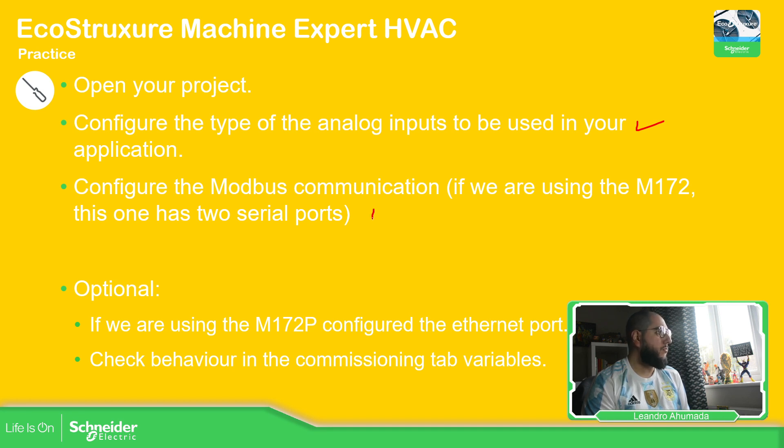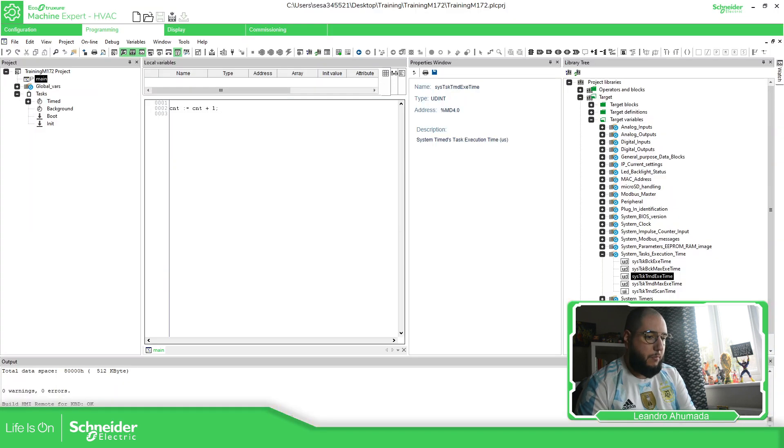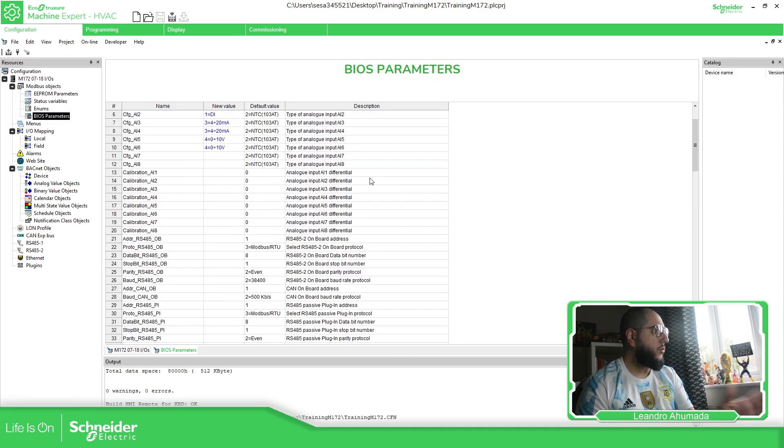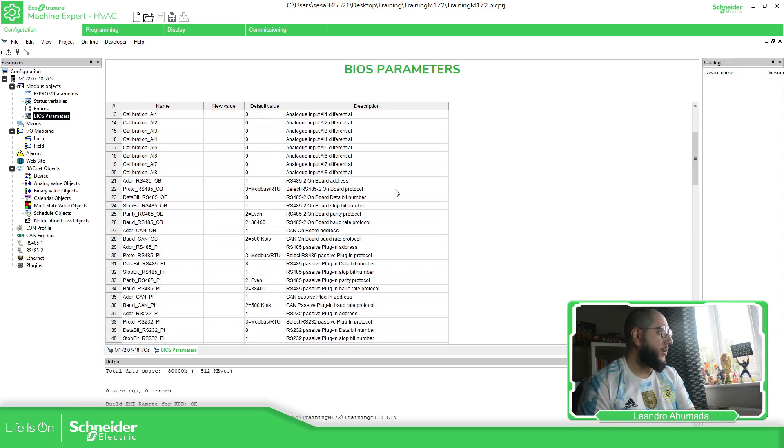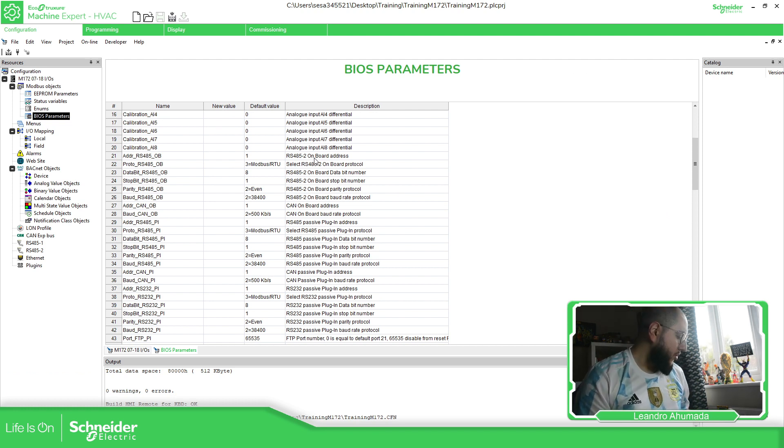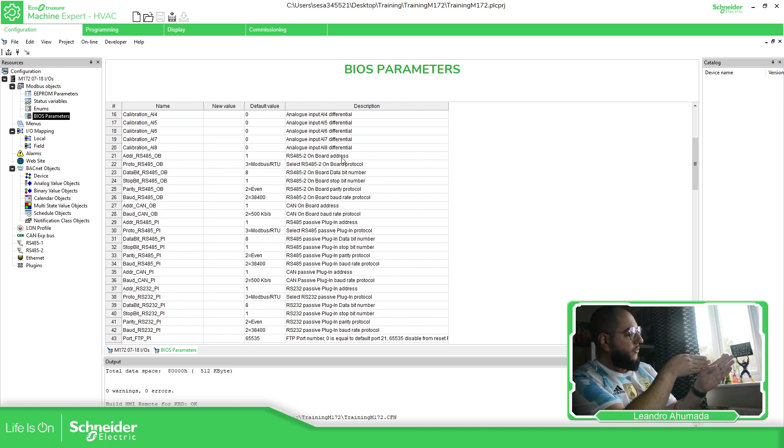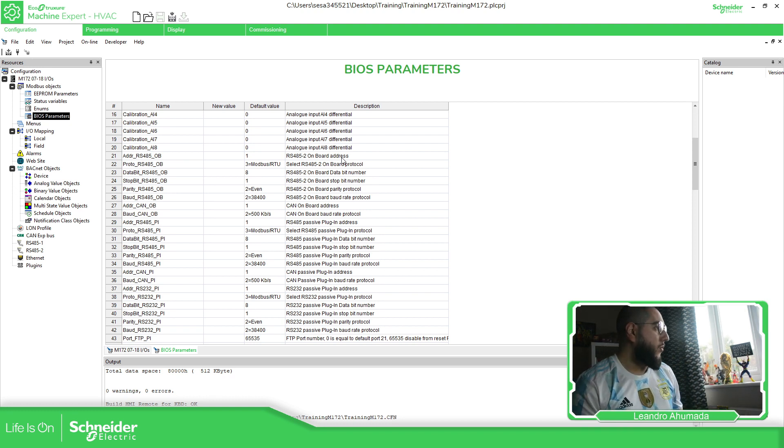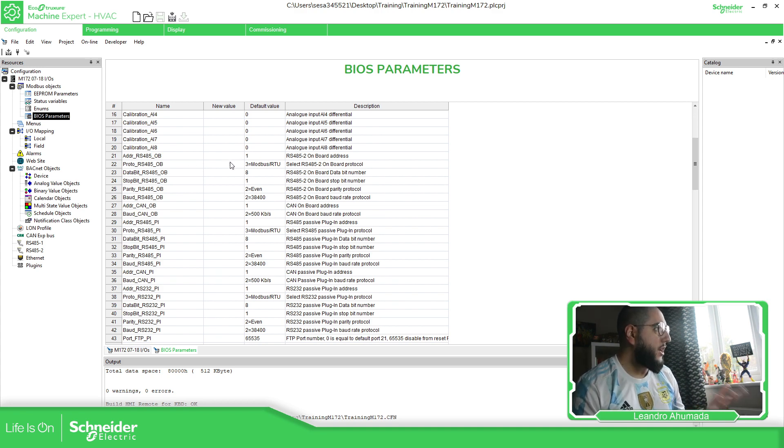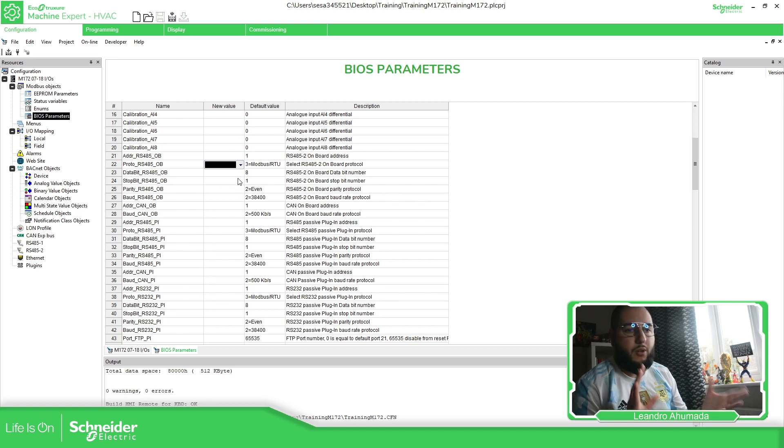So configure the type. There we go. Configure the Modbus communication. I didn't show you, but it's quite simple. Let me check something. So we have two different ports. You need to check which one is the one that you want. You have RS-485-2. Let me just check. So you have the, if you're looking at the M172 straight away in the bottom left, you have the CAN, RS-485-1, and then the 2. So this is what you need to check. And here you just select the address, the time you want, the baud rate, the stop bits, this part is easy. We are going to cover that later in the module specific for communication for Modbus.